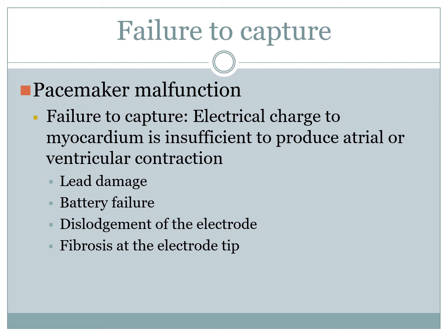Again, the things that can lead to failure to capture include battery failure, damage to the lead, and dislodgement of the electrode. One other thing here is fibrosis at the electrode tip. Remember, at the electrode tip, there's like a little hook or anchor, and that gets lodged into the myocardium, and over that first week, some scar tissue begins to form, and it keeps it in place, which is great. That's what we want to happen. But on occasion, there can be too much scar tissue that develops, and that prevents the electrical charge from the pacemaker making contact with the myocardium sufficiently enough to produce a contraction.